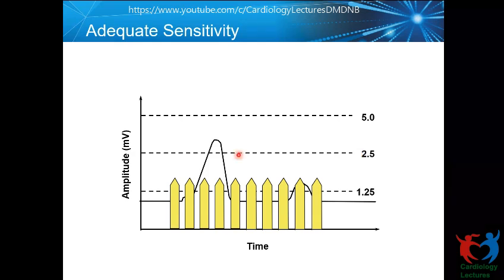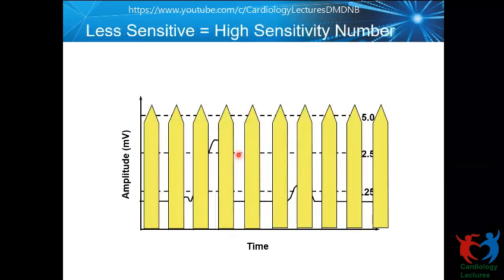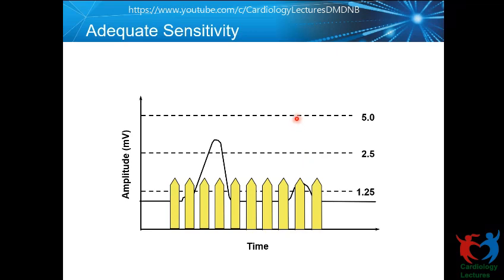let me go to this. Yeah, no, I don't have a 2.5. So if I set it at 2.5, then even when the R wave drops to 3 millivolts, as in this case, it would still sense. But if my R wave is consistently at 2, then 3, then I should not leave it at 2.5. I want to increase my sensitivity. That means I need to reduce the number. In this case, let's say 1.5 or 1.6 millivolts.